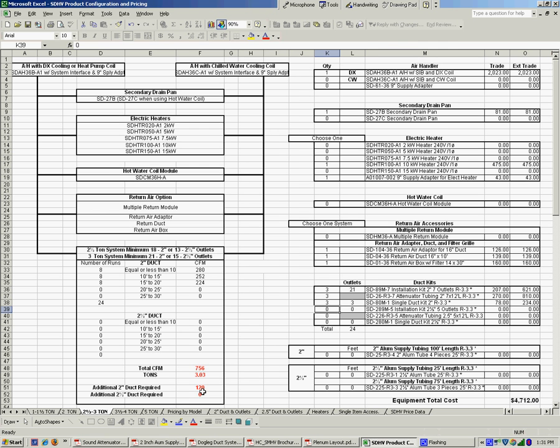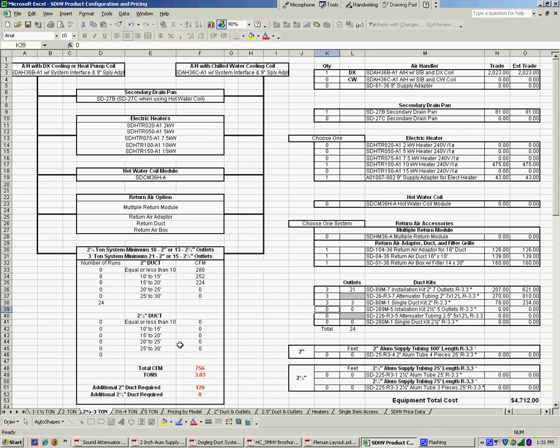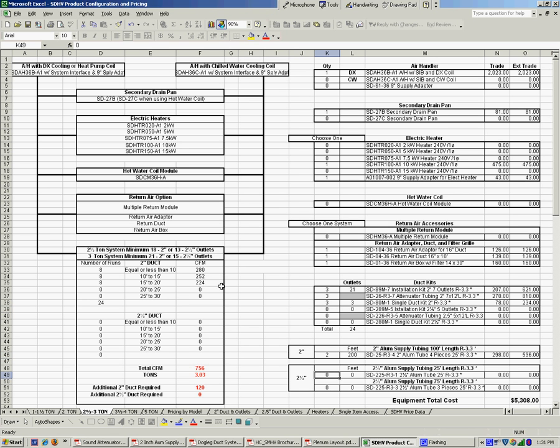Down below here it says that I need an additional 120 feet of 2 inch duct. Now remember, our attenuator piping is only 12 feet. And we've got runs that are in excess of 12 feet. In fact, I typically cut it off at 10 feet so I make sure we've got plenty of, a little extra pipe there. So it says we need an additional 120 feet of 2 inch, in this case we're going to use 2 inch flexible aluminum. We come over here and these are available in 100 foot packages. So we're going to need two of those, gives us 200 feet, and we've completed the system.